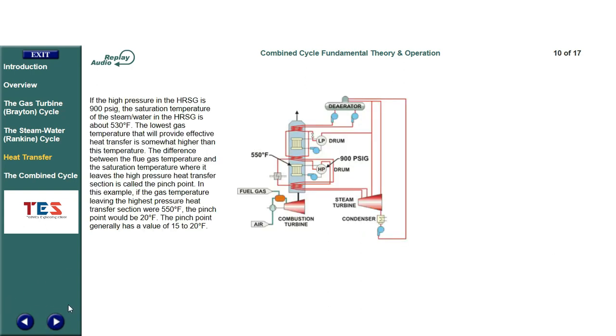If the high pressure in the HRSG is 900 PSIG, the saturation temperature of the steam and water in the HRSG is about 530 degrees Fahrenheit. The lowest gas temperature that will provide effective heat transfer is somewhat higher than this. The difference between the flue gas temperature and the saturation temperature where it leaves the high pressure heat transfer section is called the pinch point. In this example, if the gas temperature leaving the highest pressure heat transfer section were 550 degrees Fahrenheit, the pinch point would be 20 degrees Fahrenheit. The pinch point generally has a value of 15 to 20 degrees Fahrenheit.